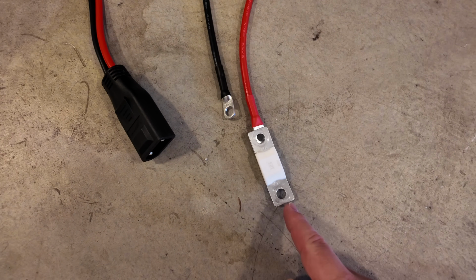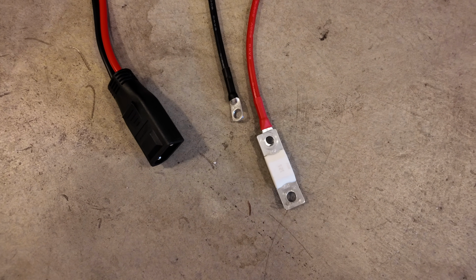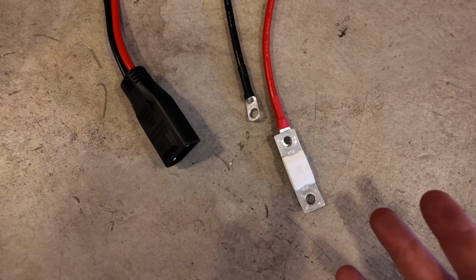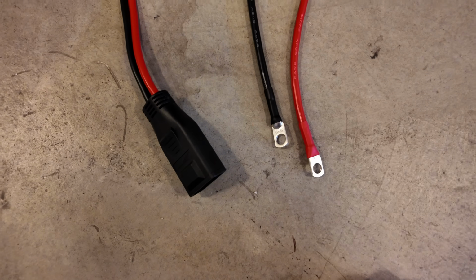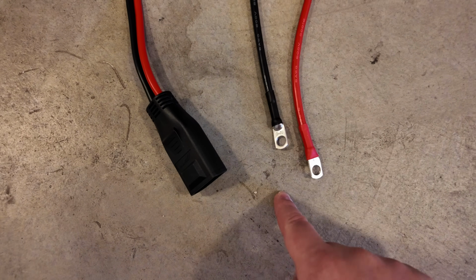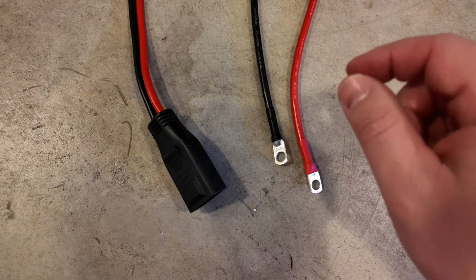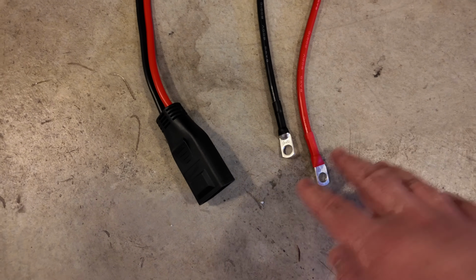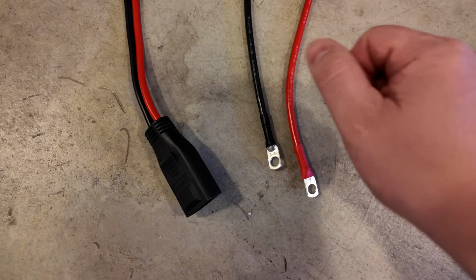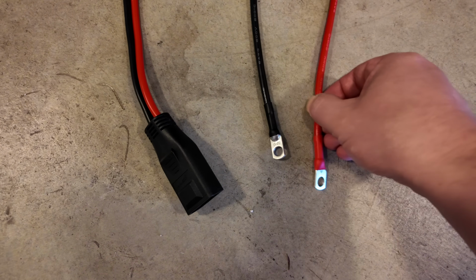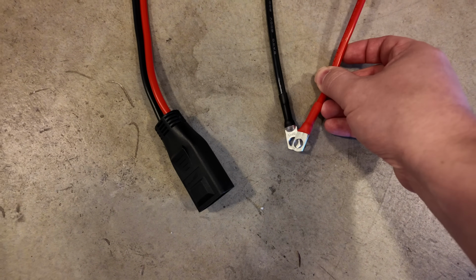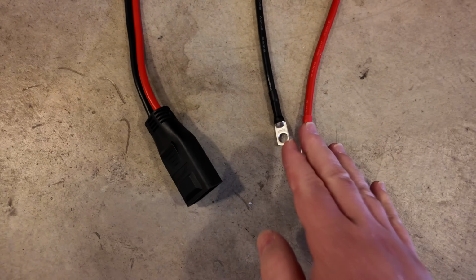The easiest way to fix that would be to get a fuse and add it to the end of the wire, then bolt it to the positive terminal of your 48-volt battery. But I'm going to show you a different approach I personally like, because it gives you overcurrent protection and also a physical switch to turn the power off, so you don't risk shorting these terminals, at least so long as the switch is off.